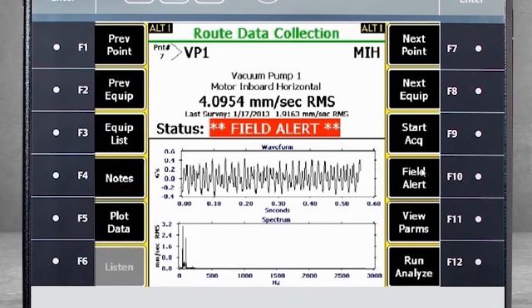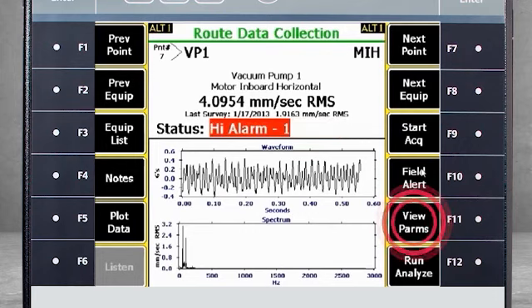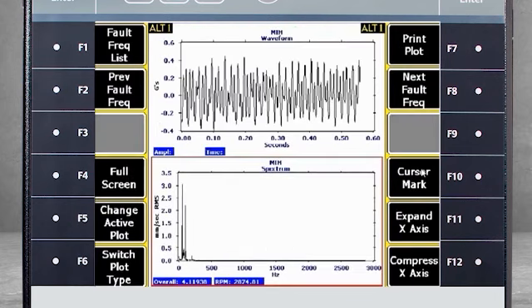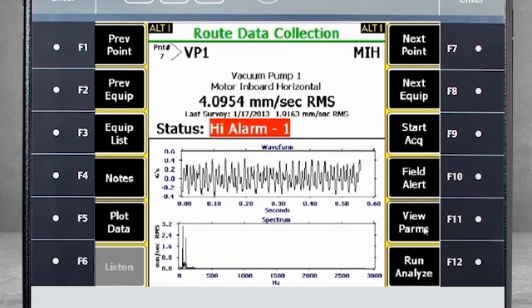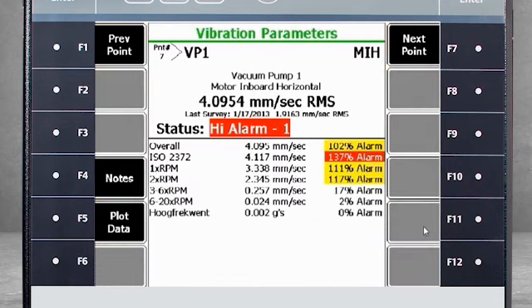F5 Plot Data will reveal the spectrum and waveform. There is a dedicated tutorial for this functionality when analyzing data on the analyzer. F11 View Parameters will display a list of all the narrow bands you have measured, along with their values and indication of alarm status. F12 Run Analyze takes you into the Analyze application where you can collect additional data with different settings such as increased resolution or a different Fmax. More details are available in a separate tutorial.